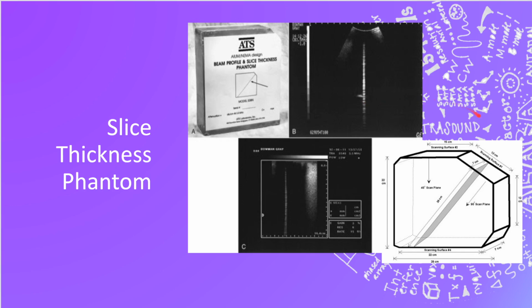Now when we come off to the side here, we would measure parallel with this beam using this slanted corner. And what that's going to tell us is how wide our beam is. So it's going to give us our beam profile. So here we can see it's very narrow in the near field.